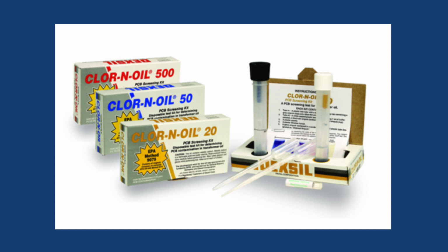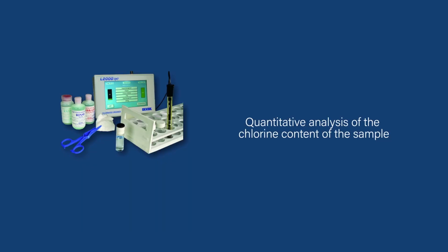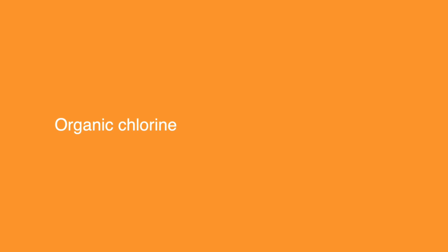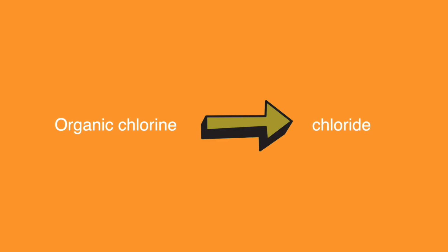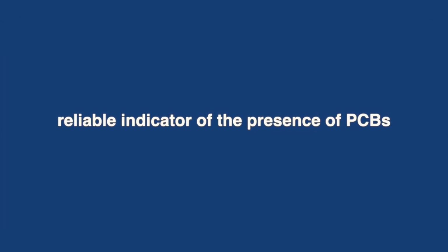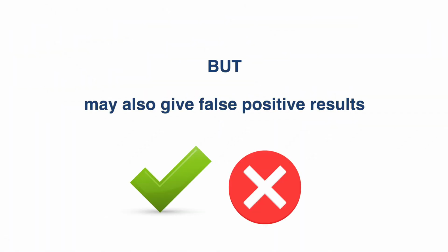Both methods do not measure PCB content directly, but provide a quantitative analysis of the chlorine content in an oil sample. They have sample preparation steps in which organic chlorine, here the PCB, is converted to chloride using a metallic sodium reagent. The analysis time for each sample is about 10 minutes for both methods. In most cases, they are a reliable indicator of the presence of PCB, but may also give false positive results when the oil has become contaminated with other chlorine-bearing substances.